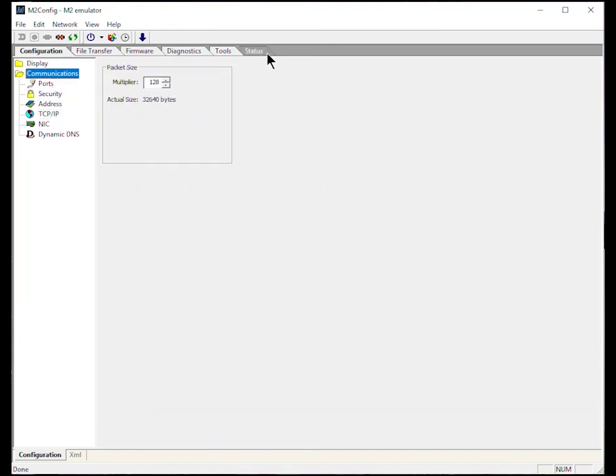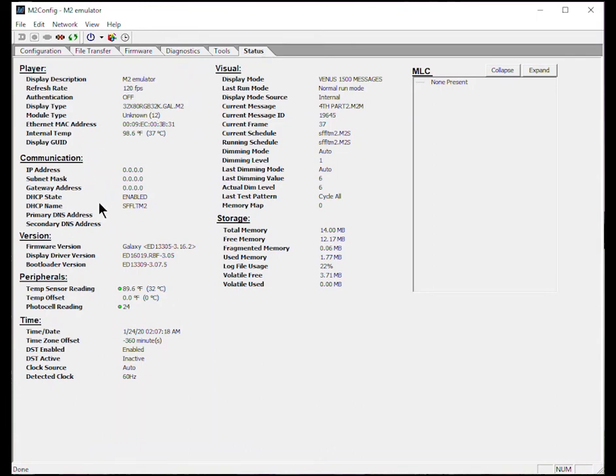We are going to wrap up this training by reviewing the Status tab. As mentioned previously, it provides a glimpse at the settings on the controller. It is important to note, when looking here, to check the firmware version, the time date, and the storage memory for fragmented memory. There is much more information displayed here that can be quickly referenced while troubleshooting, so take some time to review this for any unusual stats.